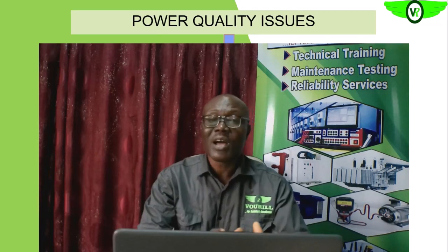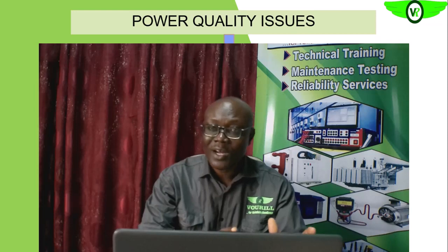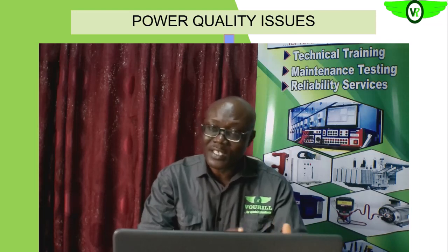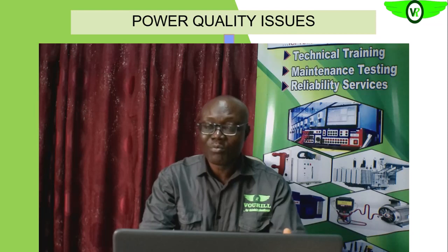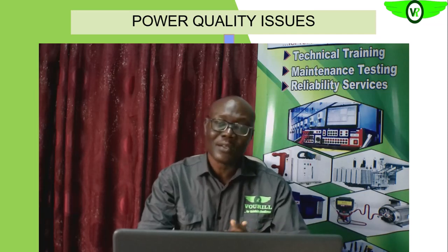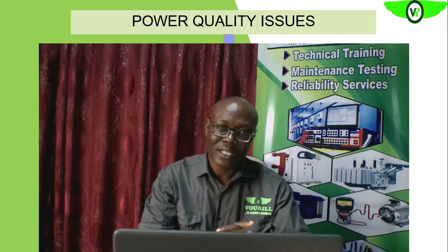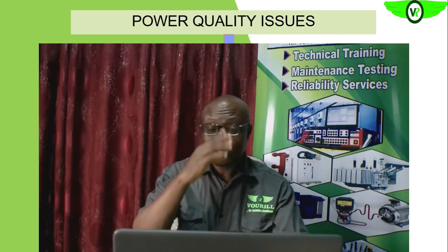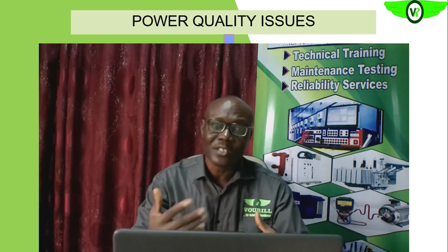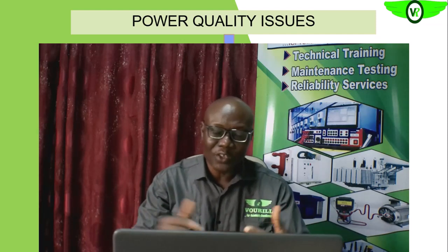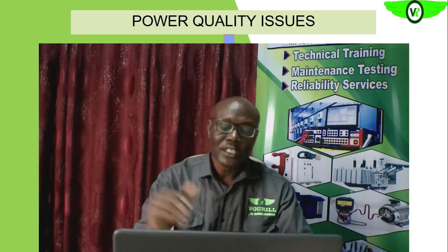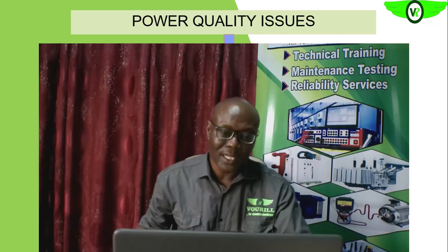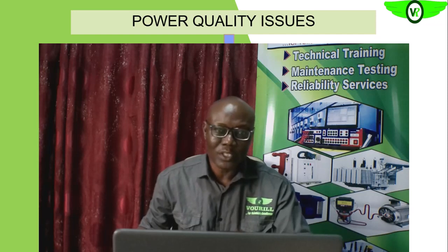So that is why under voltage is not good for our system, because it will increase the heating level of the electric motor, reduce the insulation capability, destroy the electric motor insulation, cause winding burnout. Are we getting it? Especially if the under voltage is sustained for a very long time, or it is repeated over a period of time. So the next that we are going to look at is over voltage.